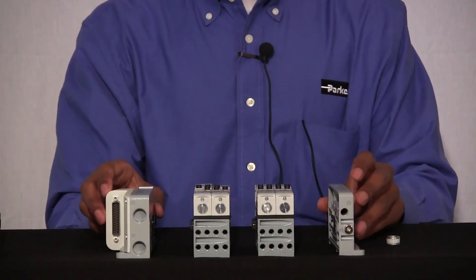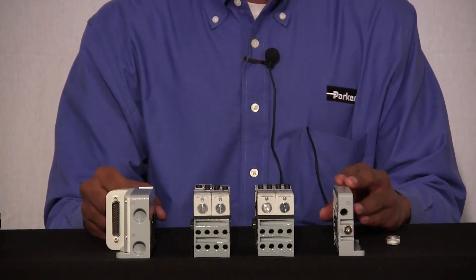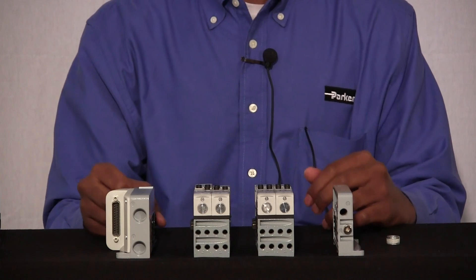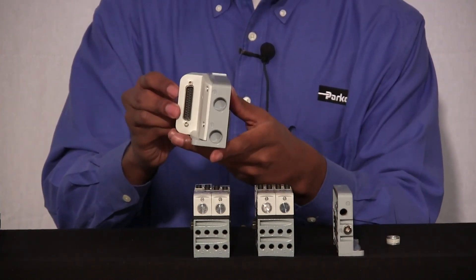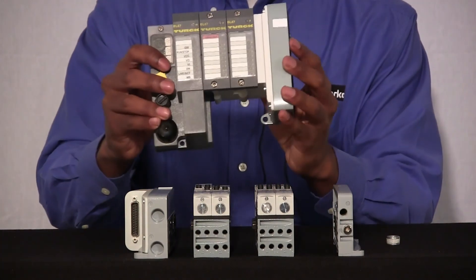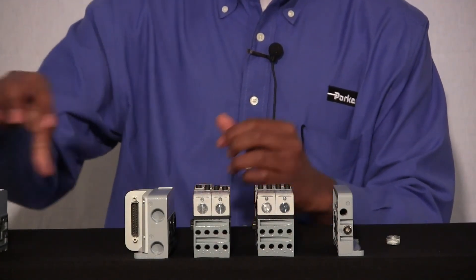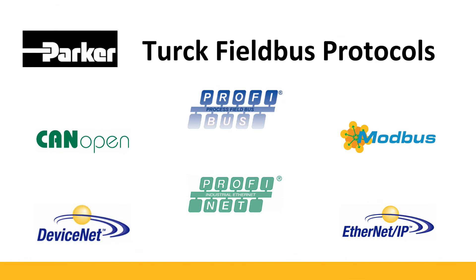Now that we've talked about the different pneumatic connections on our end plates, let's talk about the two electrical technologies that you can connect to your end plate so that your manifold valves can respond to a PLC. We offer a 25-pin hardwiring system, and we offer different fieldbus technology products that you can select from. Let's get into the three different product families we offer for fieldbus connectivity. The Turck product family allows you to connect to a wide variety of PLCs due to its ability to communicate with a large library of protocols. These protocols are CANopen, DeviceNet, PROFIBUS, PROFINET, MODBUS TCP, and Ethernet IP.